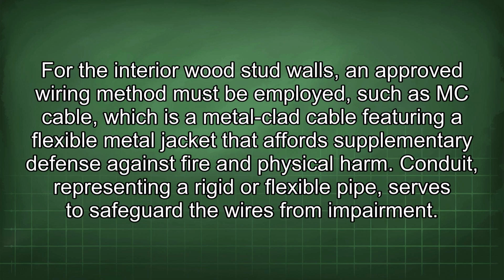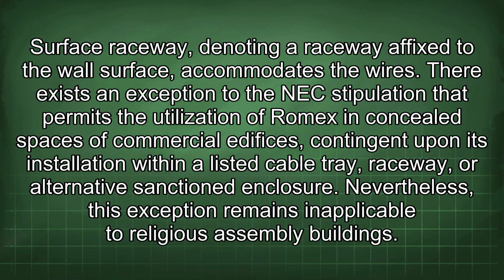For the interior wood stud walls, an approved wiring method must be used, such as MC cable, which is a metal-clad cable featuring a flexible metal jacket that affords additional protection against fire and physical harm. Conduit, a rigid or flexible pipe, serves to protect the wires from damage. Surface raceway, a raceway affixed to the wall surface, accommodates the wires.